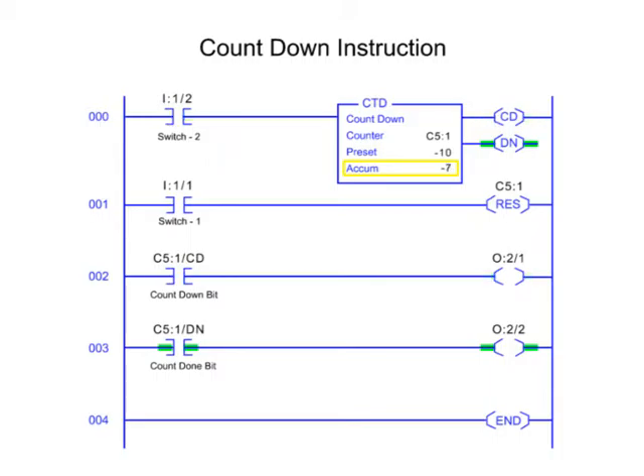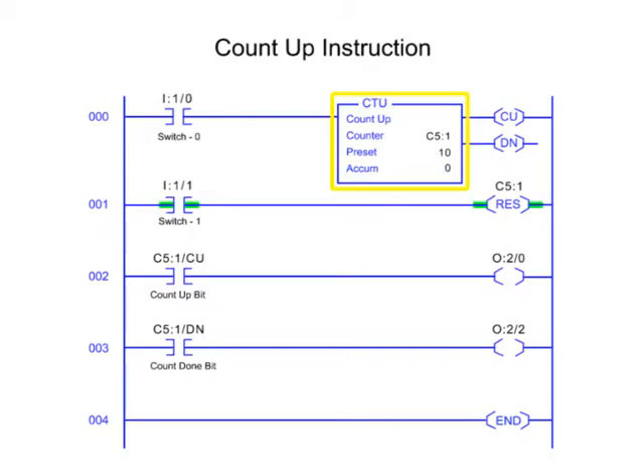After the accumulated value reaches the preset value, the counter instruction Done, or DN Control bit, is enabled. The accumulated count is retained until cleared by the Reset instruction addressed the same as the CTU file.